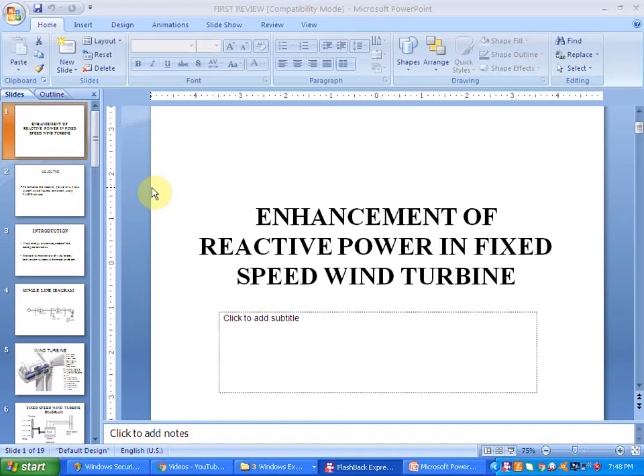In order to improve the stability of fixed speed wind generators, you can use FACTS devices. Under unbalanced grid voltages, the negative sequence voltages cause heavy generator torque oscillations. This will reduce the life of the drive train.